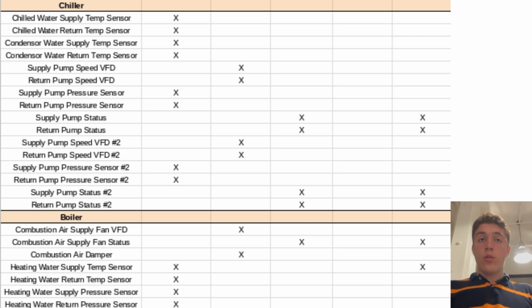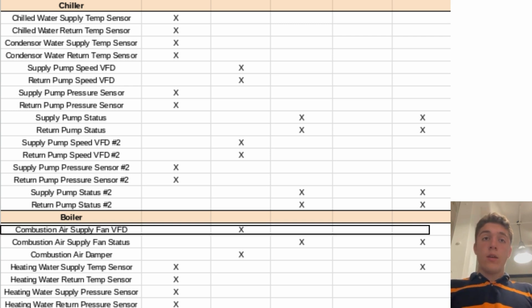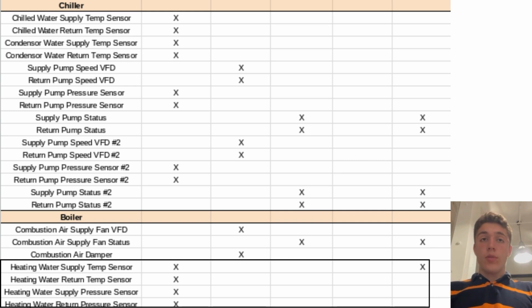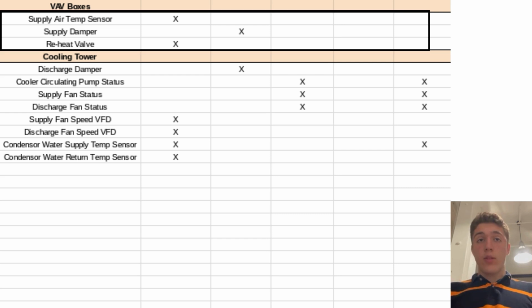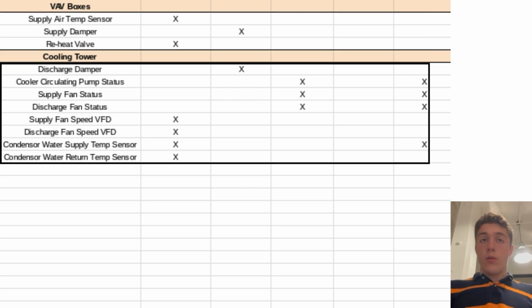Next, the boiler, there's another VFD, a damper, some temperature sensors, pressure sensors. We have the VAV boxes, we just have a temperature sensor, a damper, and a reheat valve. That's for the coil inside the VAV box that's going to be heating the air. And the cooling tower, again, we just have a damper, pump status, fan status, VFDs, and temperature sensors. So pretty standard stuff.